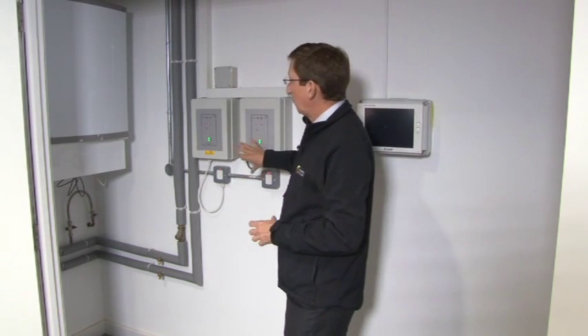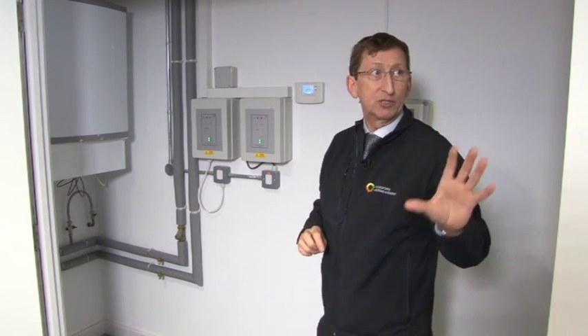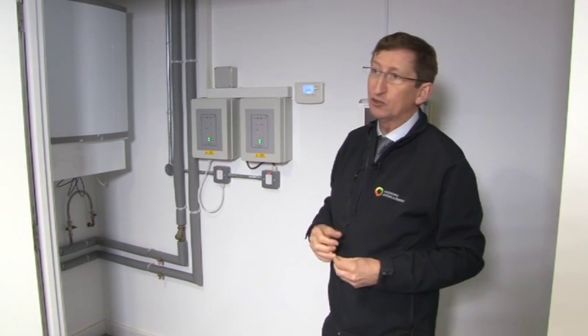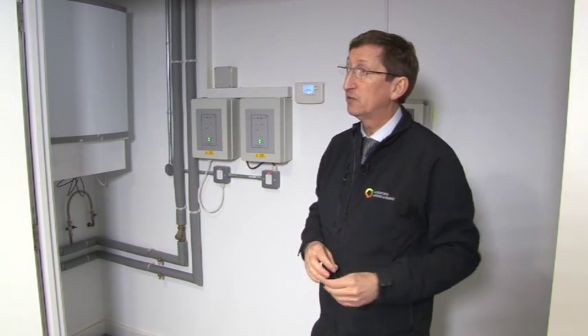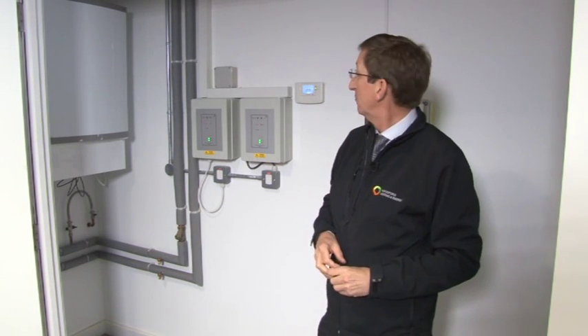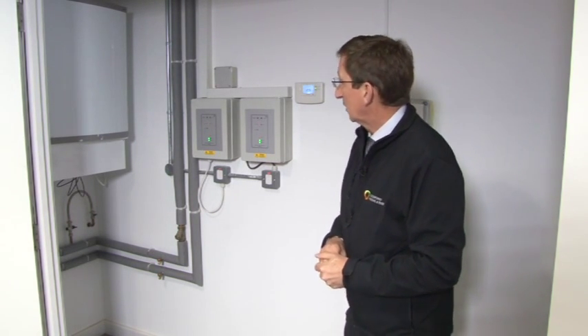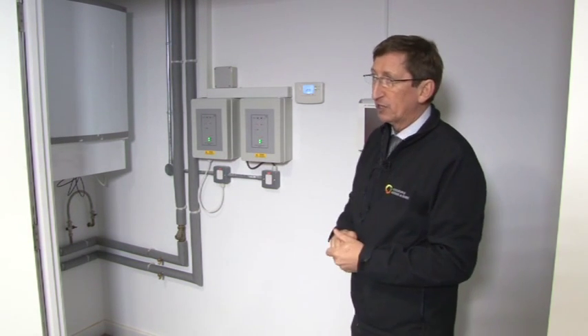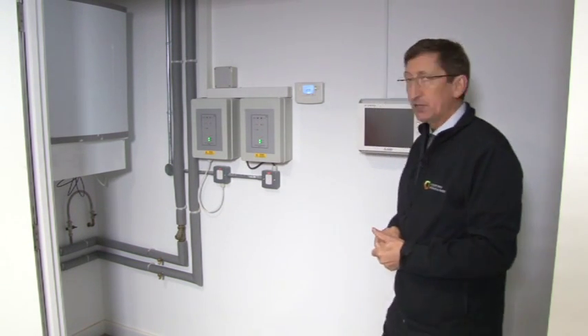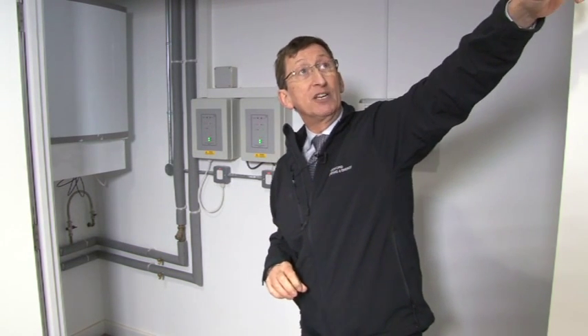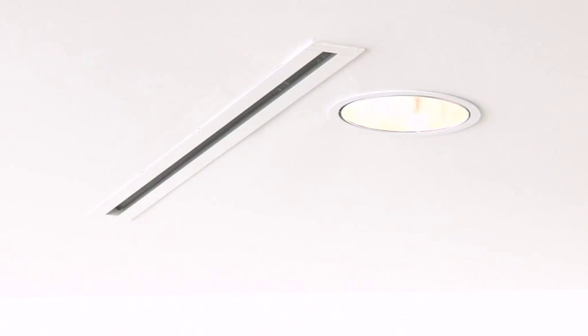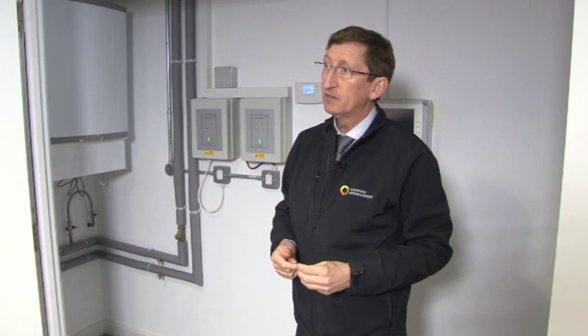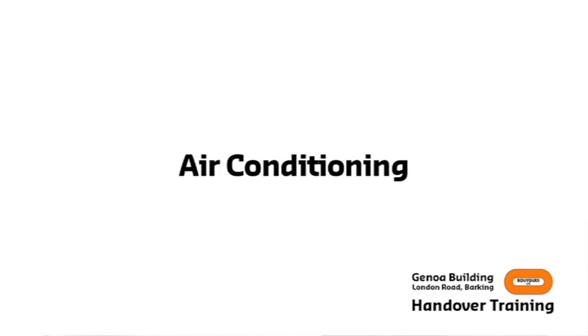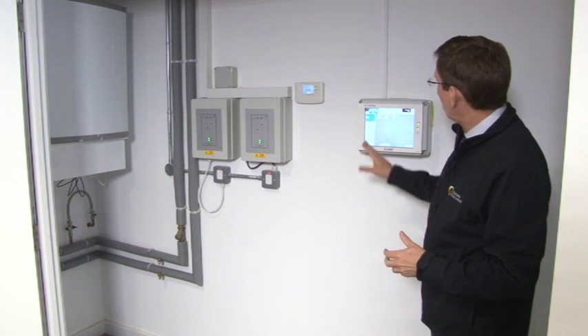There are other controllers for the heat recovery units, but they're up on the units themselves. So once that's set, that's not an alterable item as such. And they're up behind the access hatches in the ceiling of the area. Okay, so that's the second major system in the area, those heat recovery units. You can see the slot grills above the head here are where the supply is coming in, and there's some square egg crate grills where the air is going back up to the heat recovery units within the area.